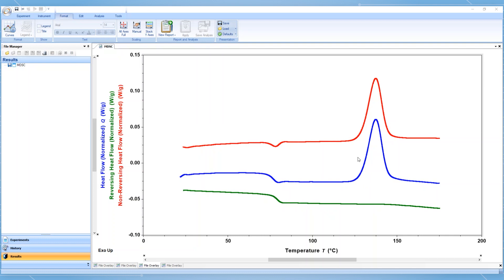If the transition occurs over too narrow a temperature range, or if the average heating rate is too fast, this minimum number of modulations might not be achieved. You can check the number of modulations over a transition by plotting the modulated heat flow of your experiment in your TRIOS software.